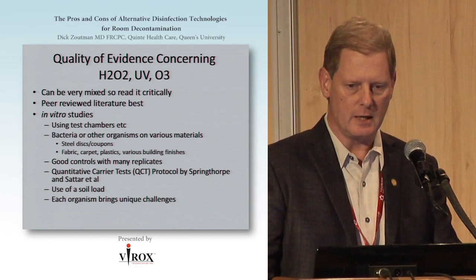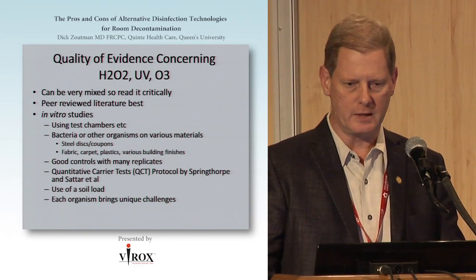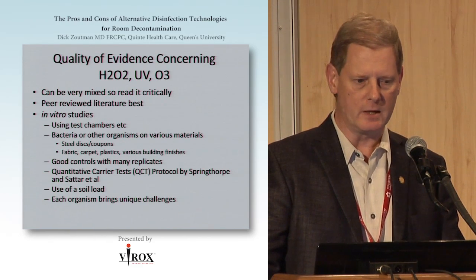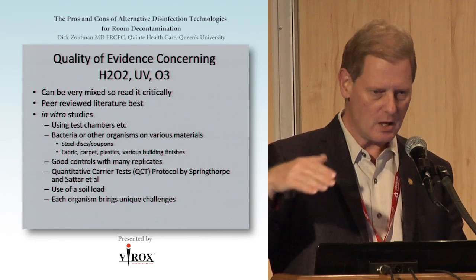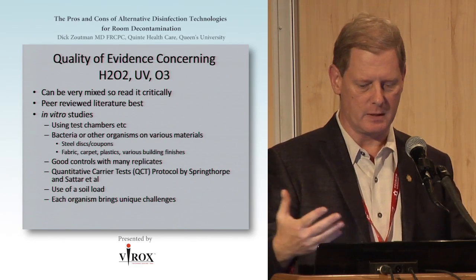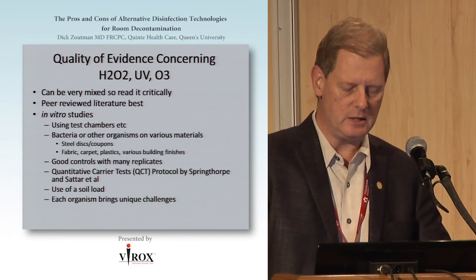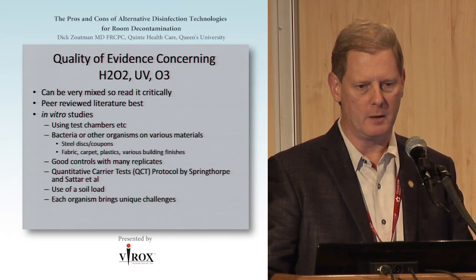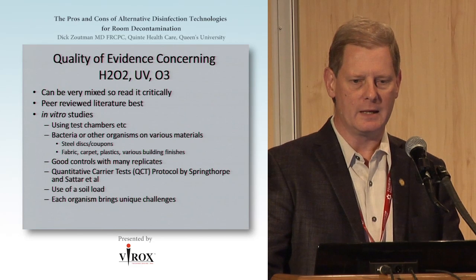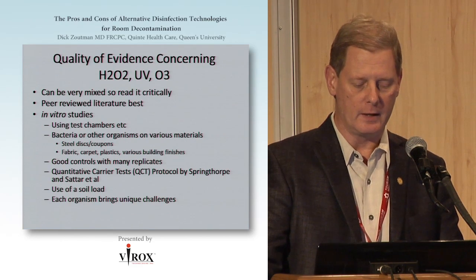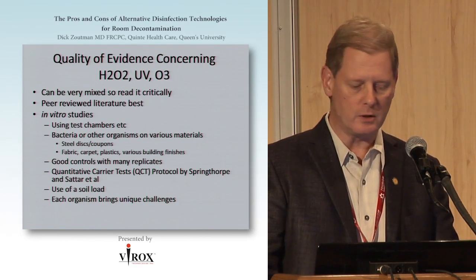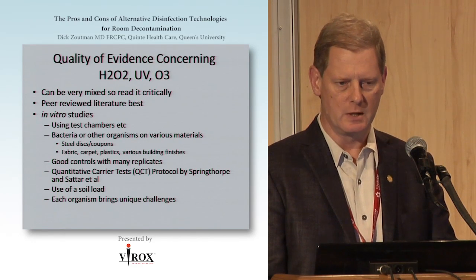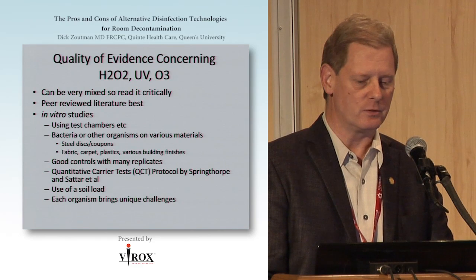The technology and the techniques going here, we owe a large debt to Dr. Sattar and the CREM group, because they have helped set the standard that has brought rigor to this, but a lot of these new techniques are requiring an adaptation of what's been developed. The QCT, or the quantitative carrier test protocols that the CREM group have promoted throughout the world, give us a lot to work with and are very useful. You do want to see a soil load test, but remember that each organism presents its unique challenges, and so they're not homogeneous by any means.